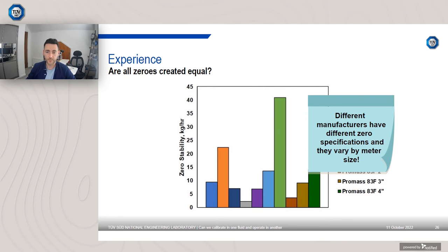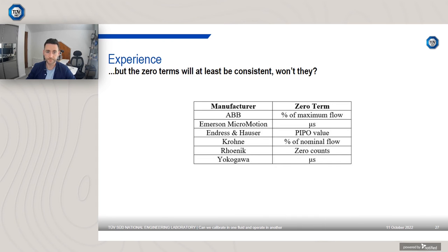But point being is different manufacturers have different zero specifications and they vary by meter size. So no, all zeros are not created equally. But the zero terms will be consistent at least, won't they? Sadly, no. Well, not sadly, there's a lot of different Coriolis manufacturers. I've only included 6 here, but to my knowledge there's at least 12 different Coriolis manufacturers. But these are 6 of the larger ones, more commonly seen at NEL and used by industry.